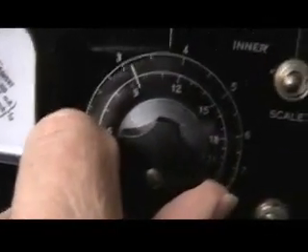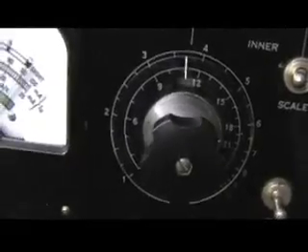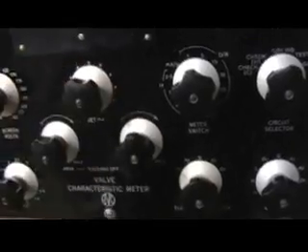Anode switch to anode 1. We're expecting perhaps a reading of about 40 milliamps. We'll leave it on 100 milliamps at full scale. Set the milliamp setting to — correction — 11.3. Finally set the main setting. We can start the test.